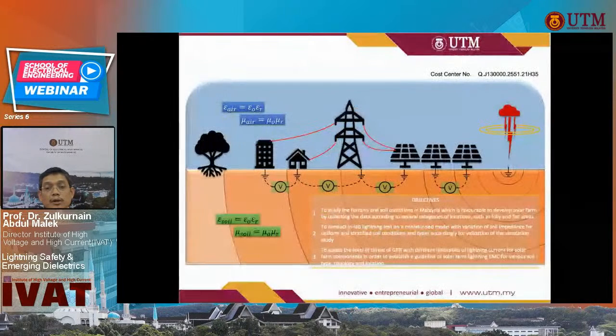So one of the components of LPS which is important is the soil itself, where we bury the ground electrode. If the soil is of high resistivity, then we may have a very high ground potential rise, because the current that flows into it will see a very high resistance, and therefore I times R will be very large. So the location of our, for example, solar farm is important, to know the soil property so that we can minimize the ground potential rise in the event of lightning.